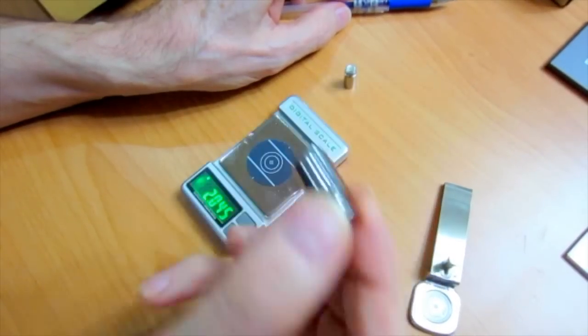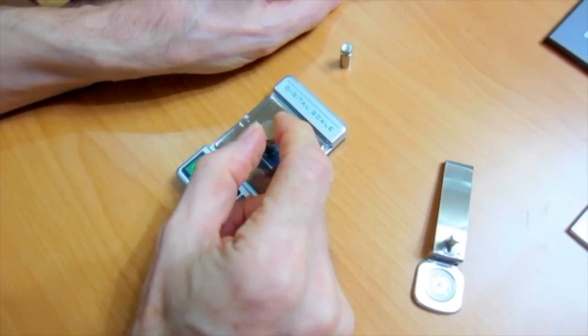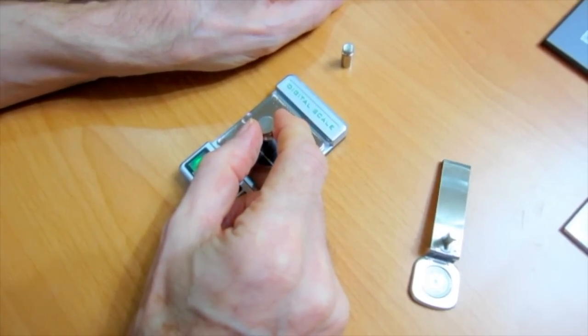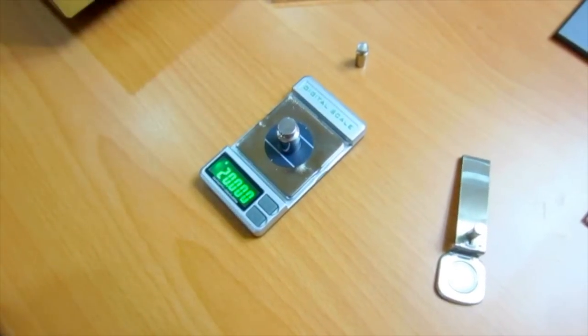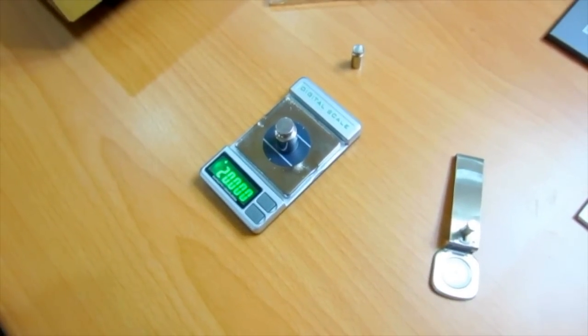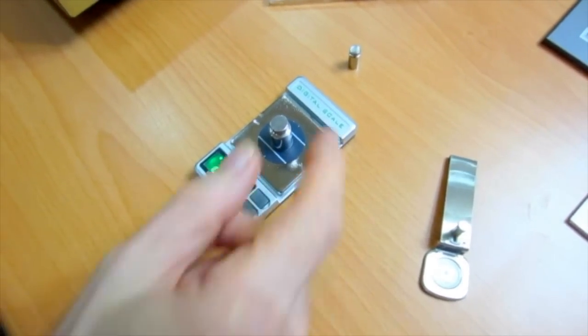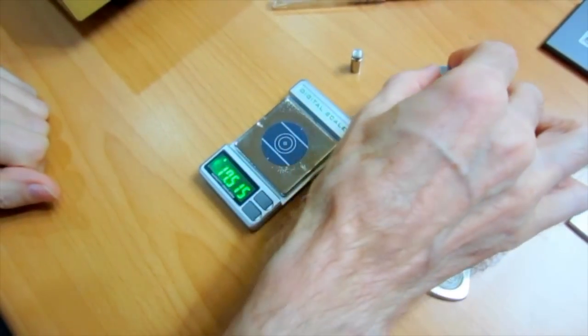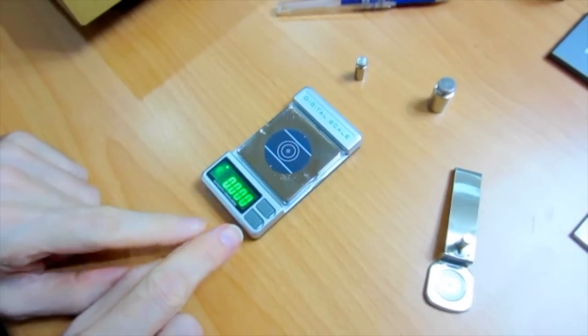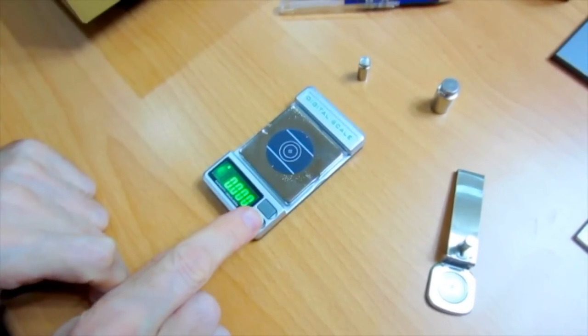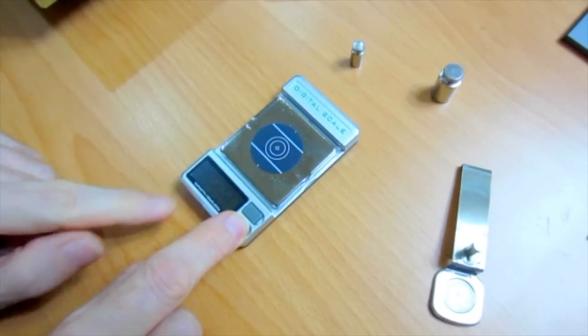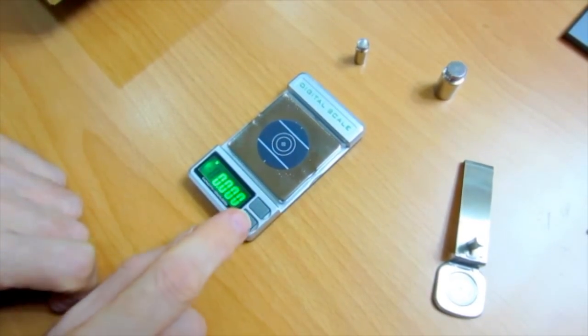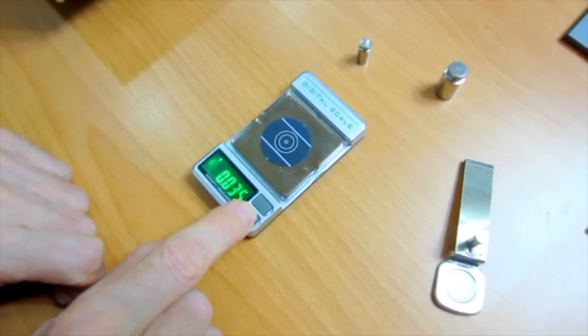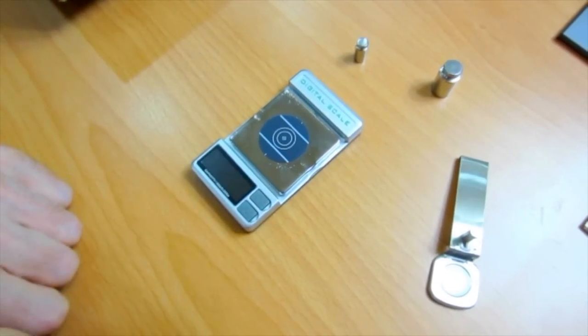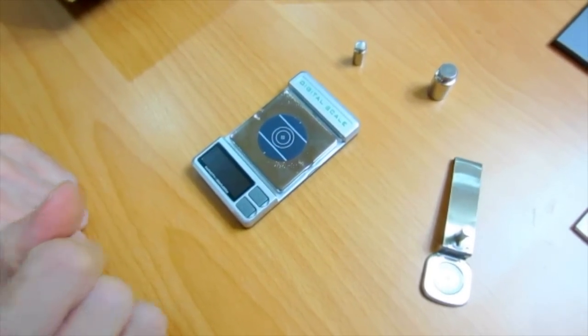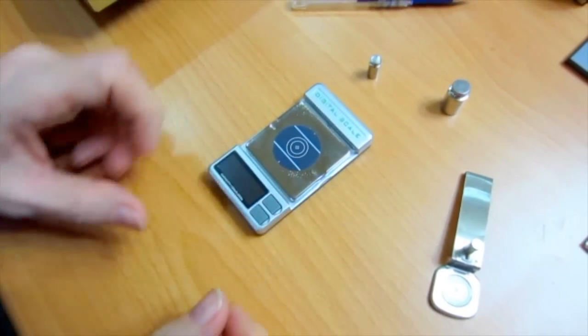Now, let's just check the calibration. Again, these are pre-calibrated, but ambient temperature can influence it. So let's just see how close we are. Well, that's fine. Alright, but again, we're going to want to go through a new calibration procedure when we put the extension arm on. So let me power this down. The way to power it down is you hold the on-off button until the screen blanks out. Let me press it. Blanked out, quickly released. It's powered down now. Alright, and if I tap it gently, it won't come back on.